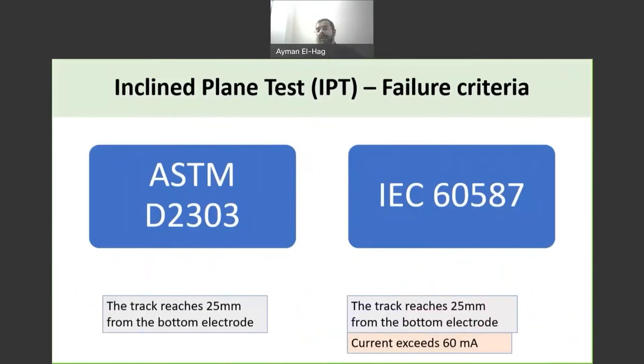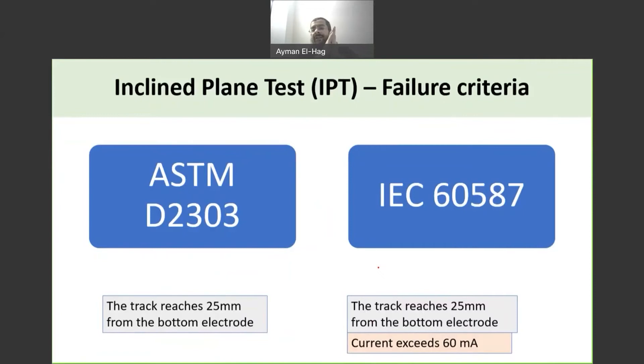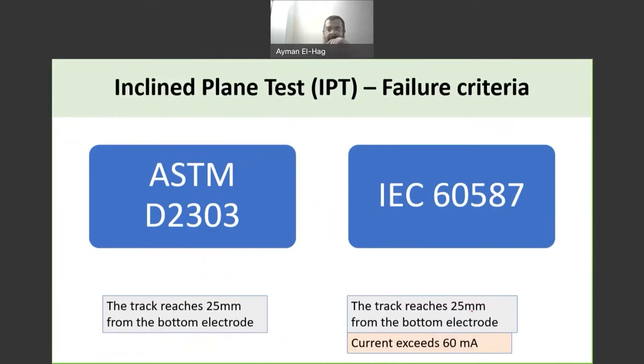What are the failure criteria? They are very similar. Both standards specify that if the track reaches 25 mm from the bottom electrode upward, the material is considered failed. The IEC also specifies that if the current exceeds 60 mA, the sample must be removed from the test — without interrupting the whole test — and that sample is considered a failed sample.